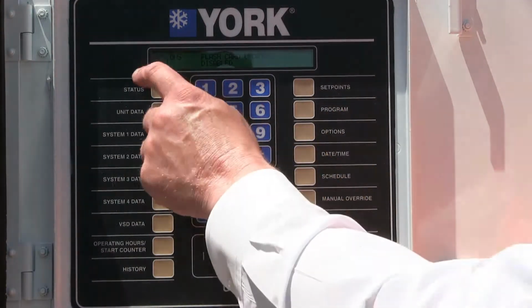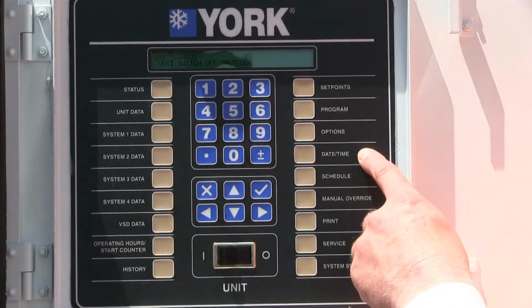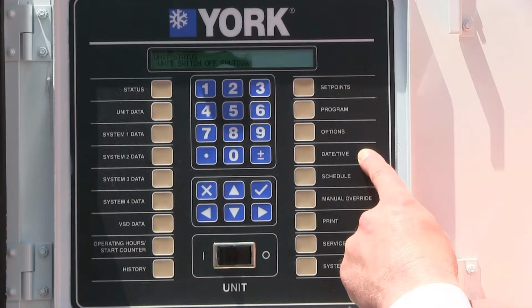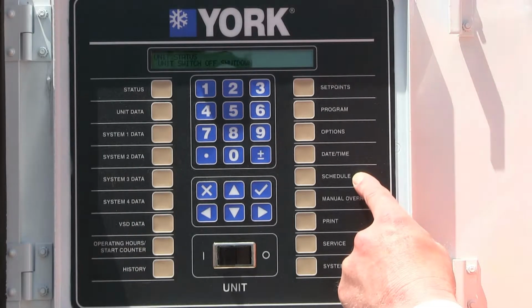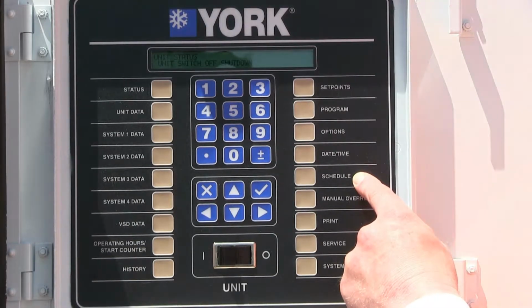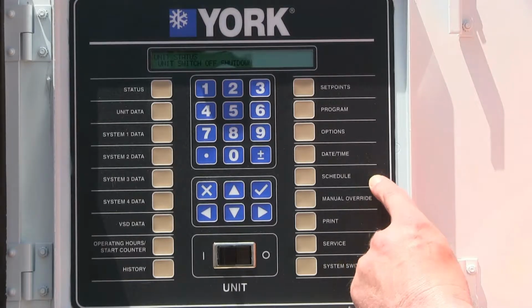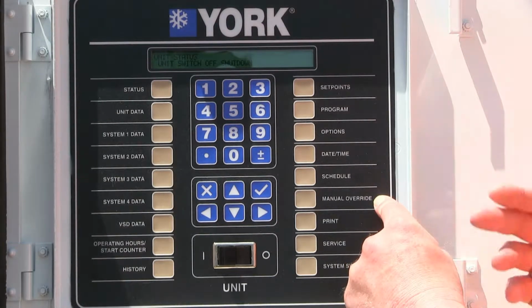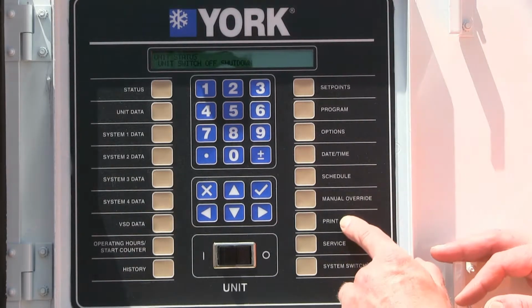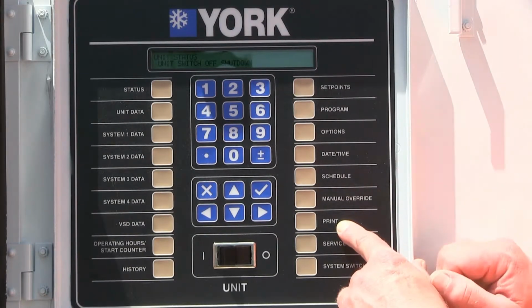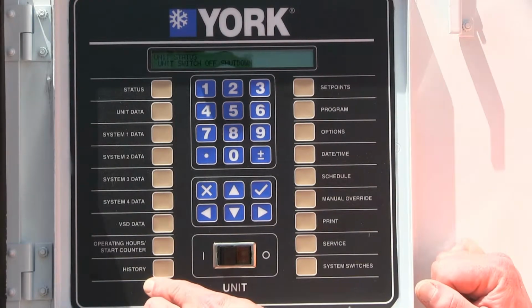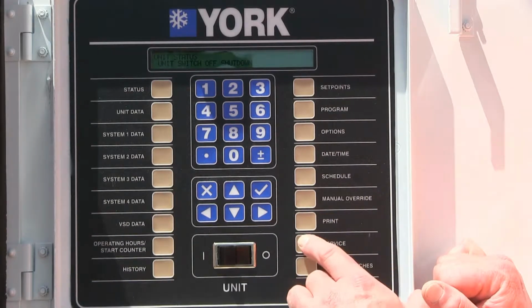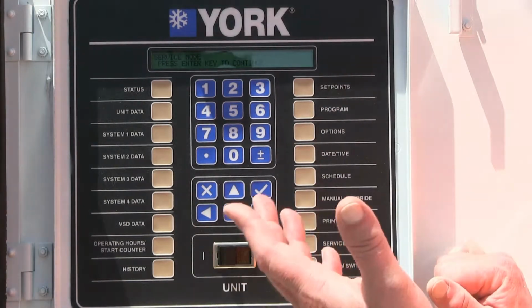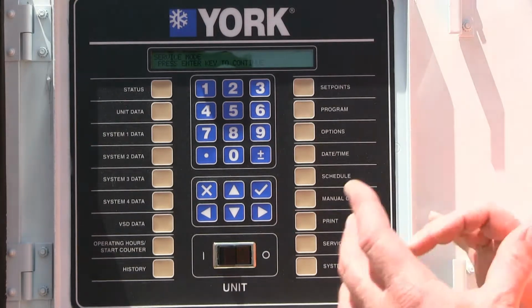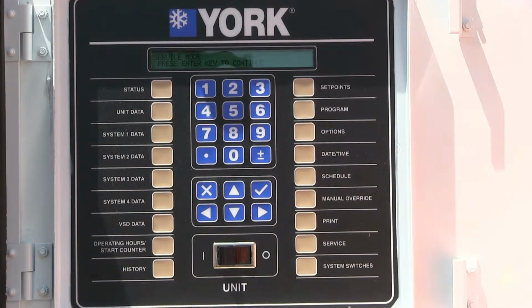But if we go back to our status here, date and time is exactly what it is. That's where we set the time and date for the machine. Schedule, if you wanted the chiller to come on at 6 a.m., go off at 6 p.m., that would be in the schedule side. Manual overrides to bypass some of the timers and start the machine. Print is if there's a plug-in printer option you have that you can print the alarm history by using that print button. The service button is an enhanced service mode that allows you to go in and look at various parameters within the chiller, from sensor settings to pressure settings.